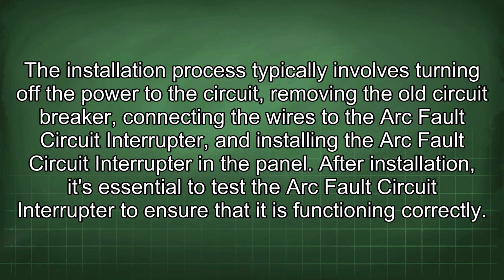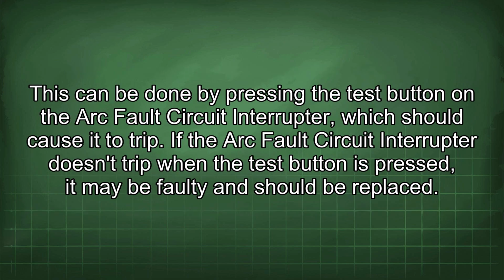The installation process typically involves turning off the power to the circuit, removing the old circuit breaker, connecting the wires to the arc fault circuit interrupter, and installing the arc fault circuit interrupter in the panel. After installation, it's essential to test the arc fault circuit interrupter to ensure that it is functioning correctly. This can be done by pressing the test button on the arc fault circuit interrupter, which should cause it to trip. If the arc fault circuit interrupter doesn't trip when the test button is pressed, it may be faulty and should be replaced.